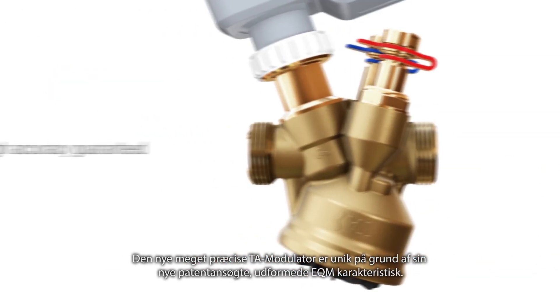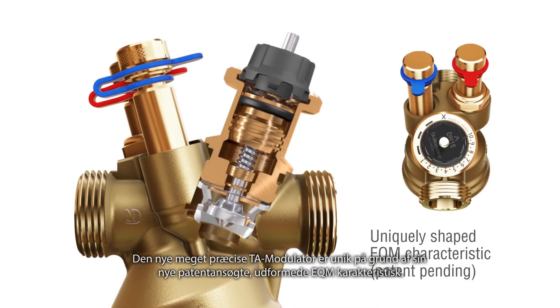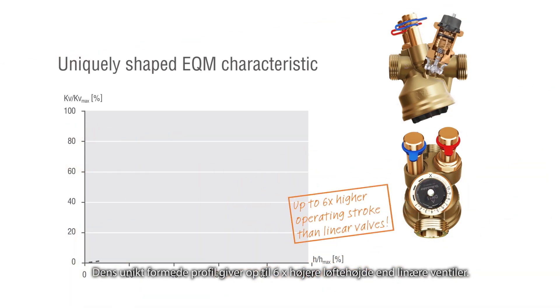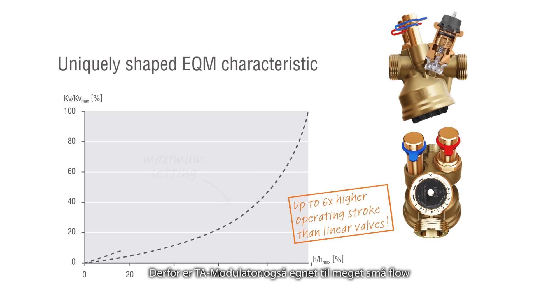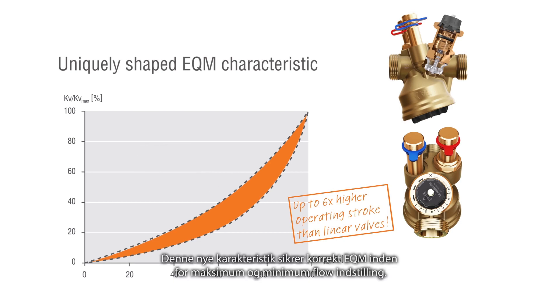The new highly precise TA modulator is unique due to its new patent pending uniquely shaped EQM characteristic. Its uniquely shaped profile provides an up to six times higher operating stroke than linear valves. Therefore, TA modulator is able to precisely control also very small flows. The new characteristic remains equal percentage within the range of maximum and minimum flow settings.